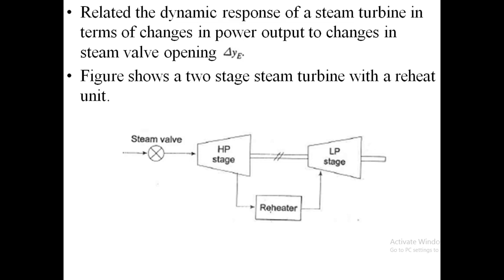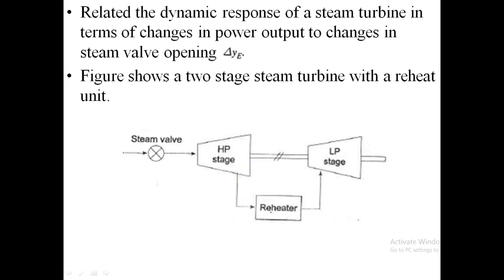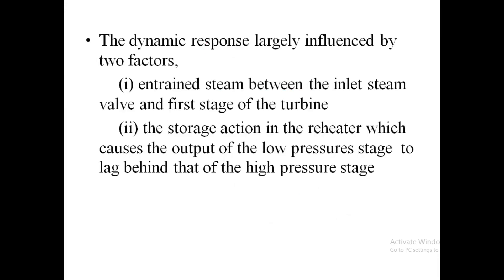Now we are representing the steam turbine — a two-stage steam turbine with a reheat unit. In this diagram there is a steam valve, a high pressure and low pressure stage, and a reheater. The dynamic response is largely influenced by two factors: one is the steam between the inlet steam valve and the first stage of the turbine, and the storage action in the reheater which causes the output of the low pressure stage to lag behind that of the high pressure stage.